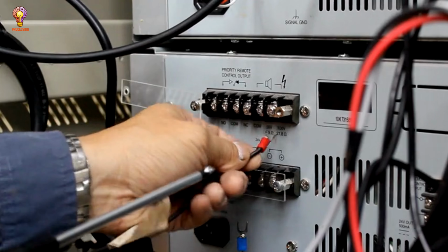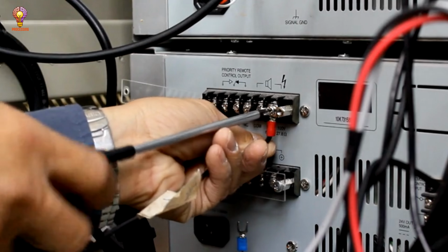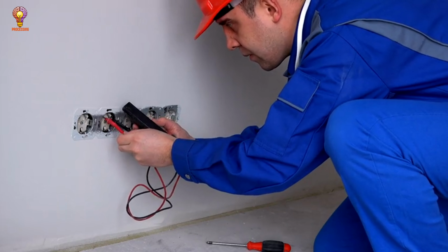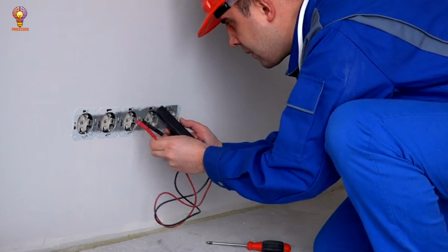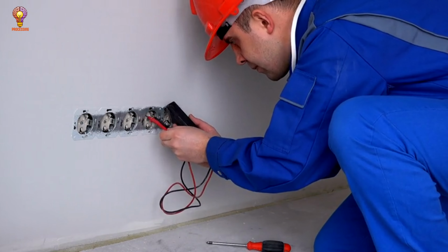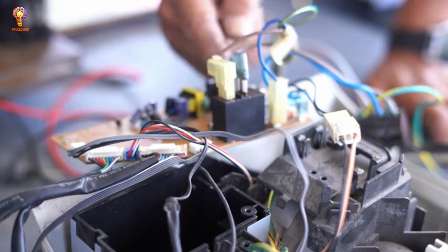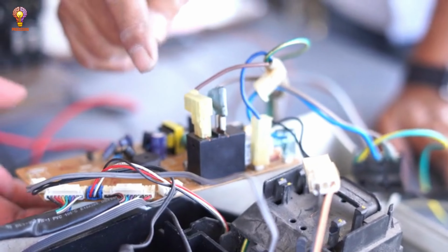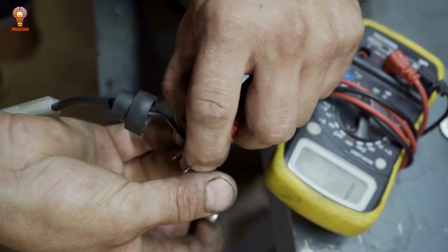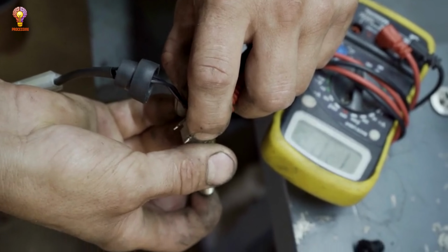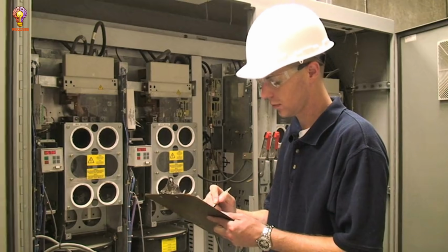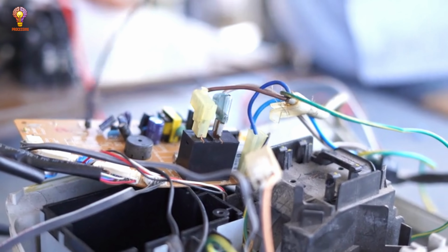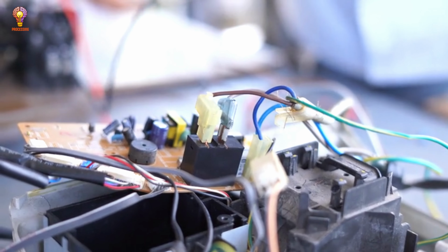10. Maintenance and troubleshooting. Proper maintenance is key to preventing power cord failures. Some aspects of cord maintenance include regular inspections. Technicians or safety officers perform regular visual inspections of all power cords. They check for signs of fraying, exposed wires, burns, or any other visible damage. Testing. Factory personnel often use testing equipment such as multimeters or continuity testers to check whether power cords are functioning properly. These tests can detect issues like broken conductors or poor connections that may not be immediately visible.